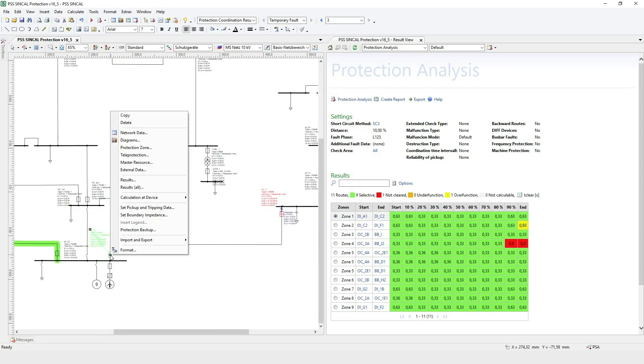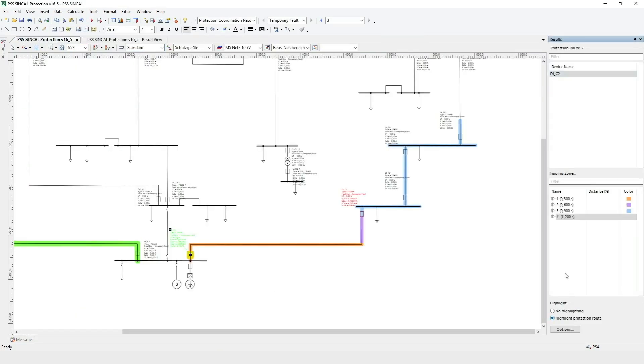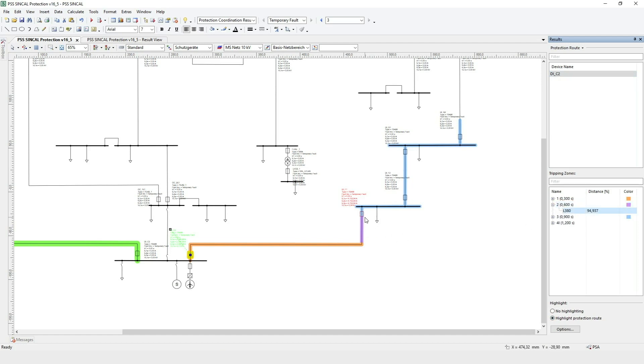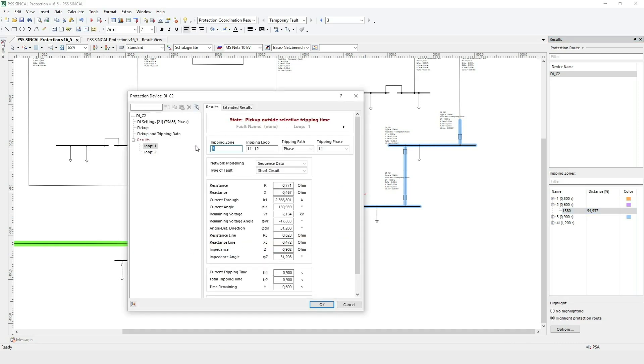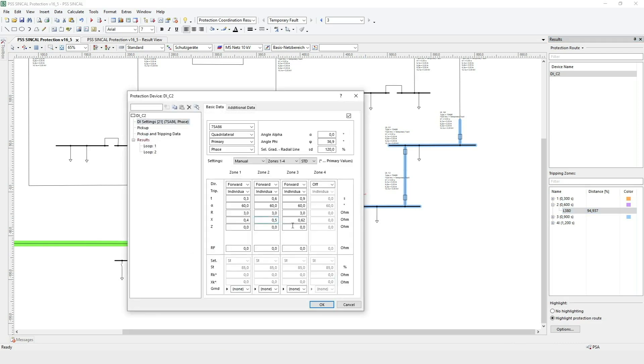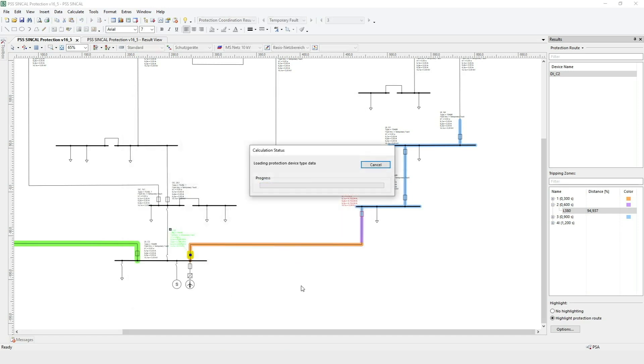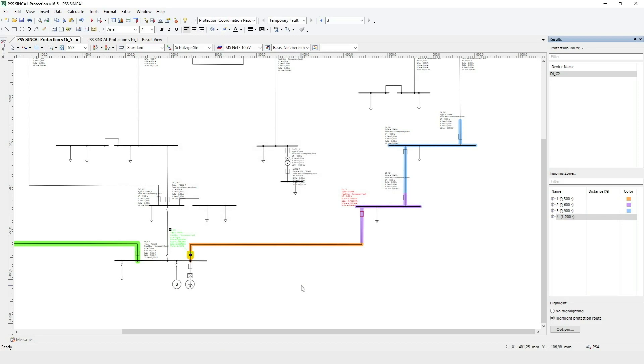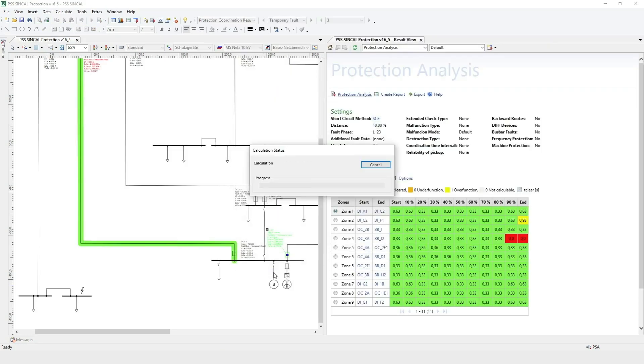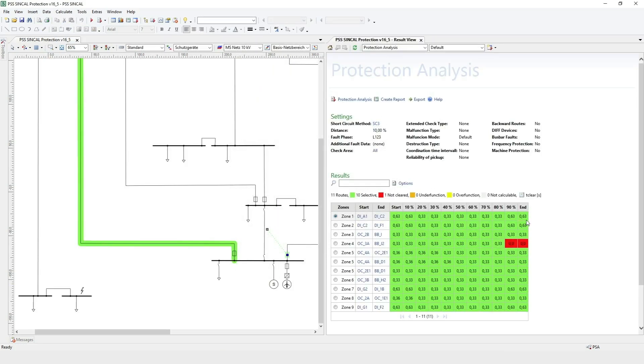Right-click on the device, then choose Calculation at Device, and select Protection Route. We see the second zone of the distance protection device, shown in violet, only covers 94%. But this zone should cover at least 100% of the main protection area. With this information, we know the second zone isn't set correctly. Let's adjust the settings and change zone 2 to 0.5 ohm and perform a protection route calculation again. Now the second zone covers 100% of the main protection area and part of the following protection area. When we perform the protection analysis again, the over-function disappeared.